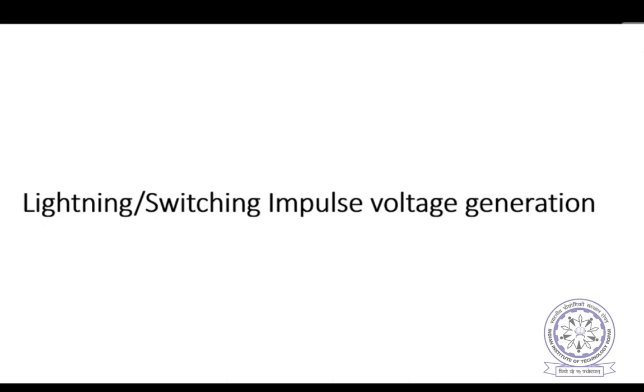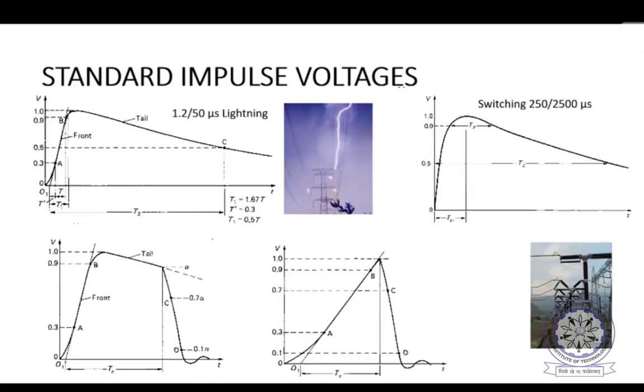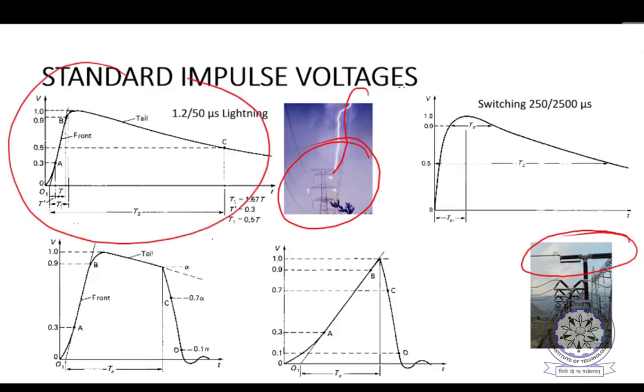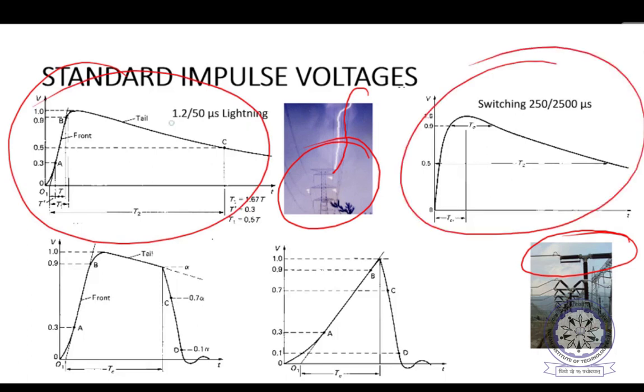Now the last one is lightning or switching impulse voltage generation. There are 2 types of impulse voltages I already told you. One is lightning, this transmission line tower you can see here. Another is switching, when a circuit breaker opens or closes or in a fault condition. So this is the lightning standard impulse and this is the switching standard impulse. Only the times are different. 1.2 by 50 microseconds is the lightning impulse: 1.2 is the time to reach the peak and 50 is the time to tail. Lightning impulses are shorter in time than switching. Switching is actually 250 to 2500 microseconds. 250 is the front time and 2500 is the time to tail.